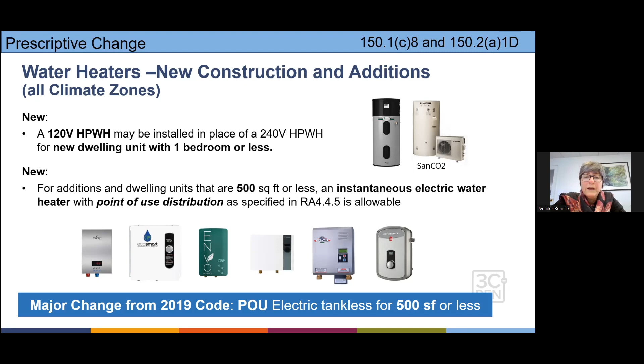On the next slide, I'm going to show you what that point of use distribution looks like and what that means. So if you do choose to use it, the point of use distribution is saying you need to put that water heater right near the fixtures that are going to be using the hot water. And these hot water pipes do need to be insulated. And there is a table that isn't part of the code that tells you how long of pipe you can have based on the nominal diameter of the pipe size. So in this particular example, if you had one of the Stiebel Eltron water heaters, they have a 3/4 inch line coming out of the heater.